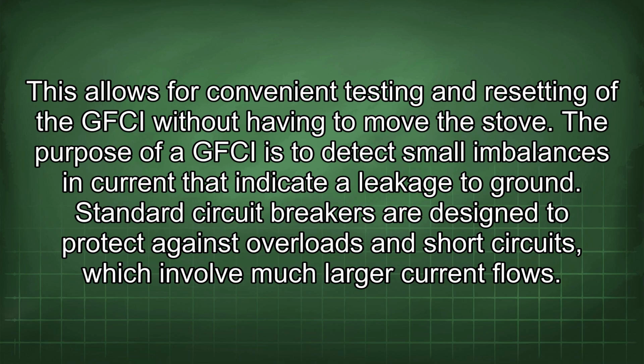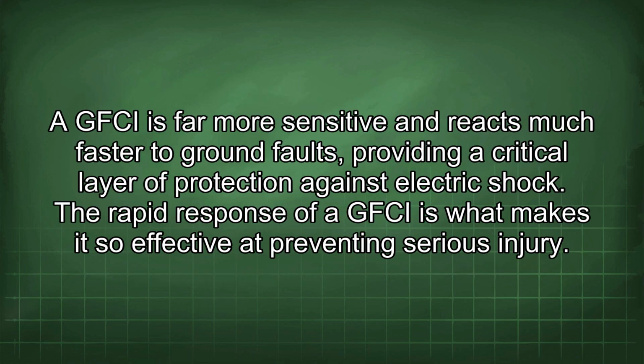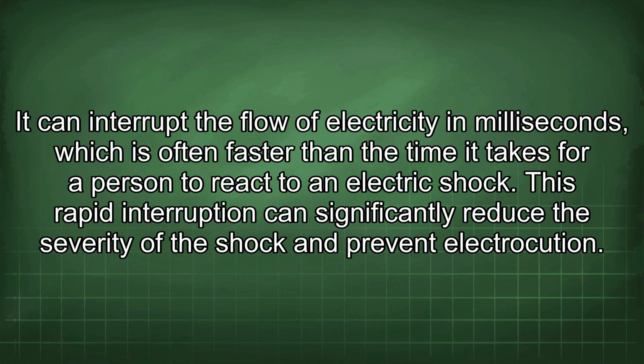The purpose of a GFCI is to detect small imbalances in current that indicate a leakage to ground. Standard circuit breakers are designed to protect against overloads and short circuits, which involve much larger current flows. A GFCI is far more sensitive and reacts much faster to ground faults, providing a critical layer of protection against electric shock. The rapid response of a GFCI is what makes it so effective at preventing serious injury. It can interrupt the flow of electricity in milliseconds, which is often faster than the time it takes for a person to react to an electric shock. This rapid interruption can significantly reduce the severity of the shock and prevent electrocution.